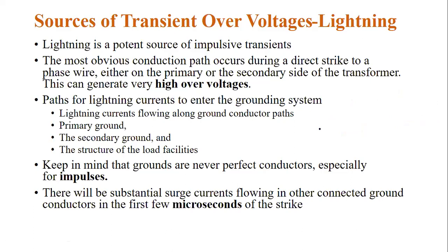So then what are the paths? Now the important thing: what is the main path for lightning currents to enter into the grounding system? As I said, each and every pole and each and every equipment is connected by ground. But remember, grounding does not entirely protect equipment from lightning. Grounding only minimizes the effect of the lightning or over voltages or impulses produced in the system.